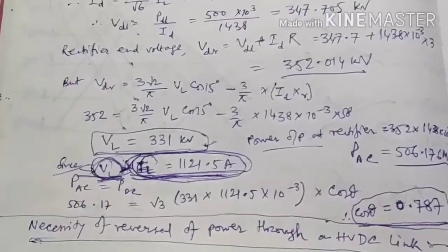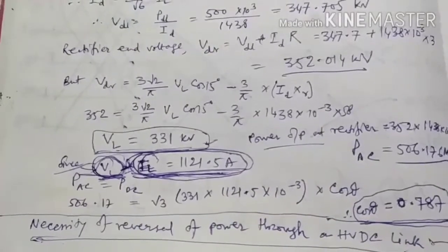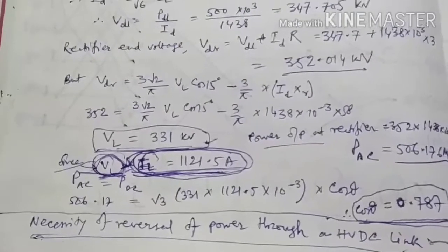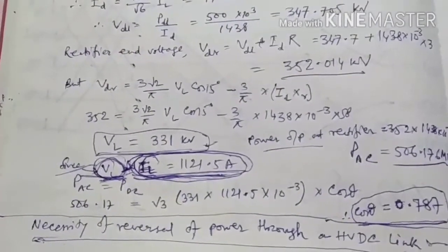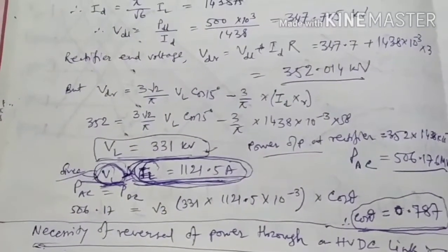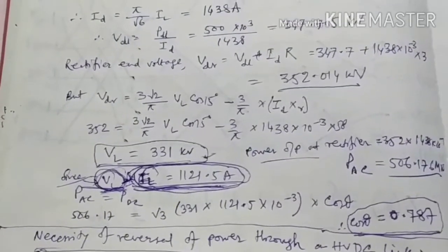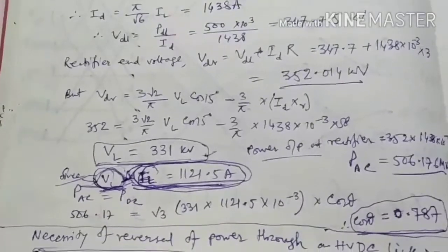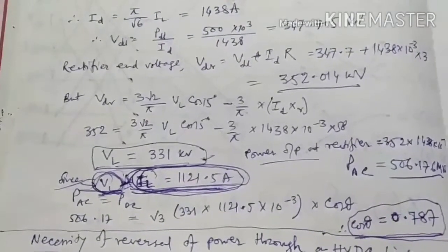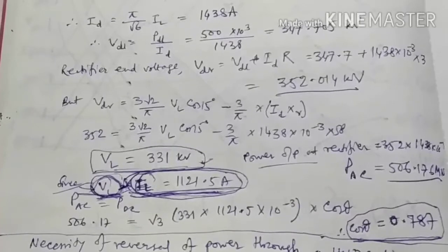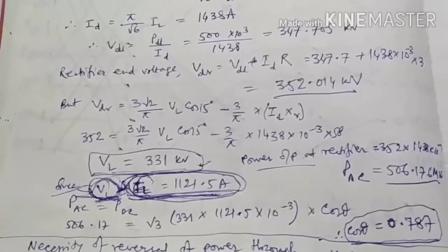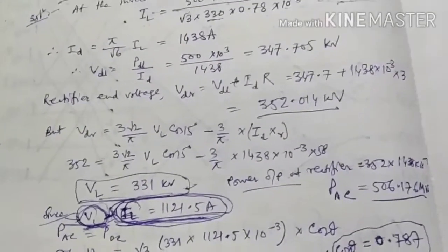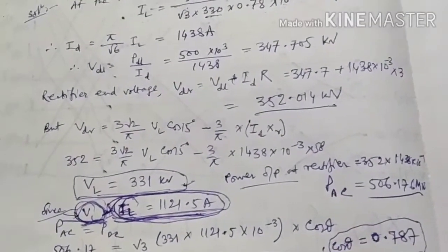And third, fault on an HVDC line pole, during which the line is temporarily de-energized by changing over the rectifier to inverter. After a certain lapse of time, attempts are made to re-energize the line by changing it to rectifier. This operation requires the ability of each converter to operate as a rectifier or an inverter.